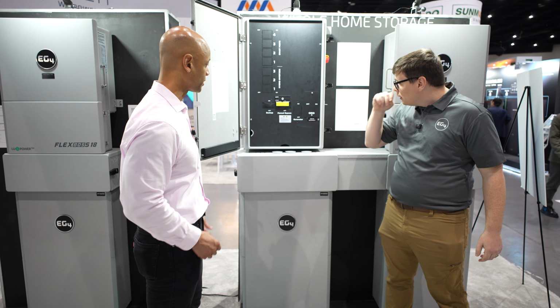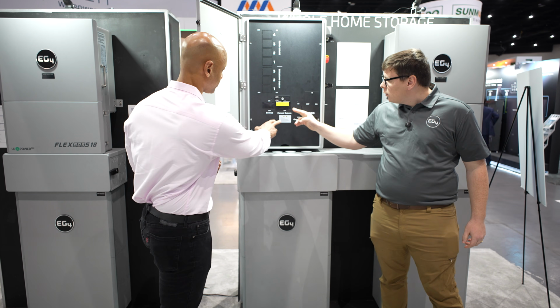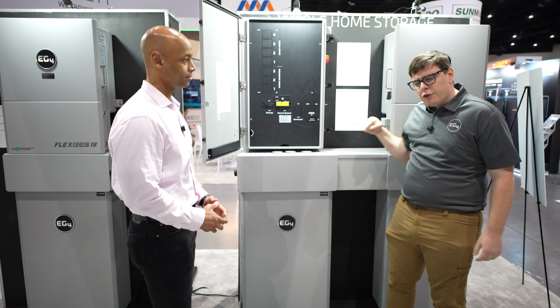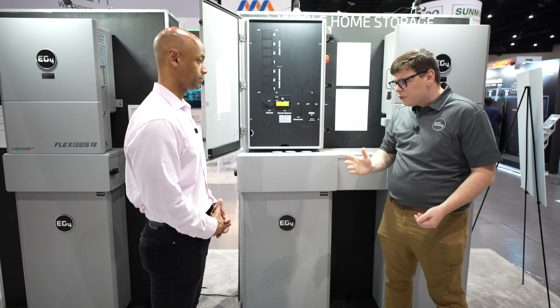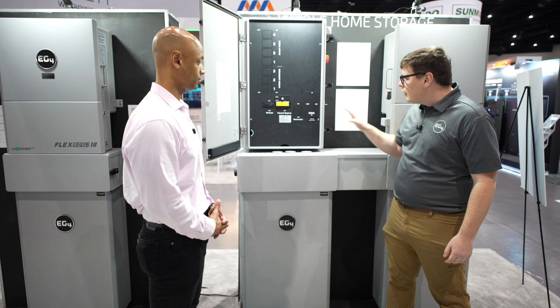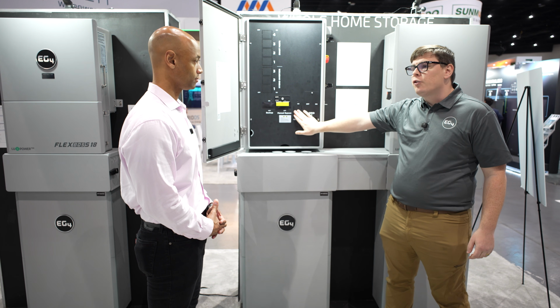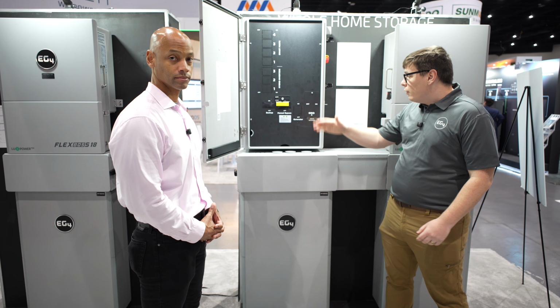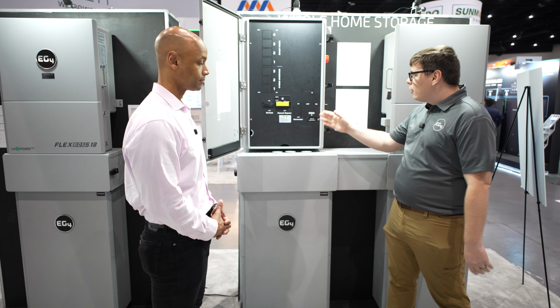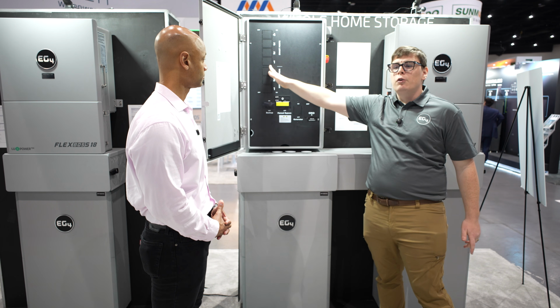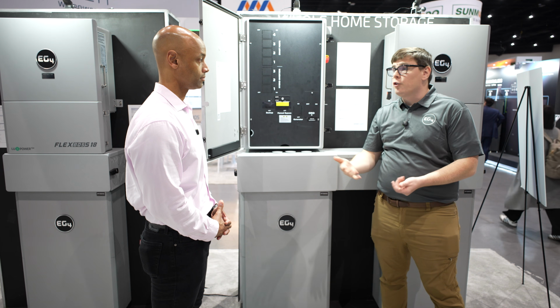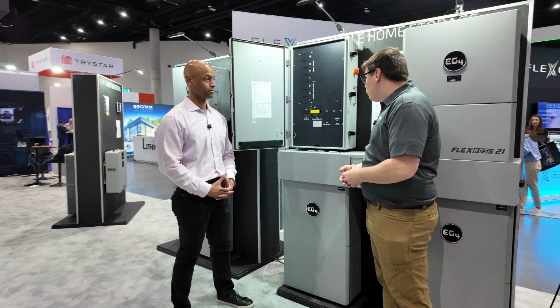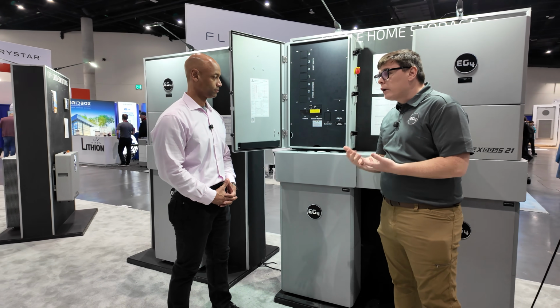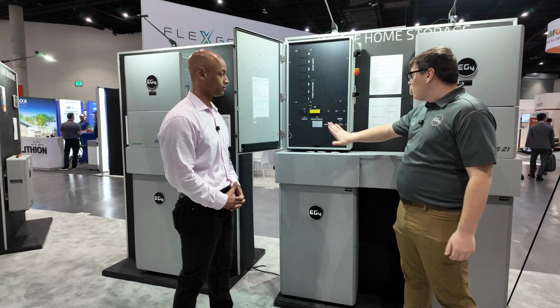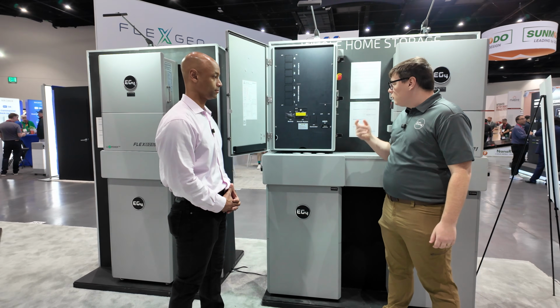What are some of the other functions that the GridBoss supports here? I see a bypass. The manual bypass, that changes your 200 amp transfer switch, is built into this solution. And it also has the generator integration built on here, so you can add in a separate generator directly into here. You can load shed here, and you can also AC couple. So you can do all 3 at once. Whatever the customer needs, whatever you're looking for as a homeowner, this is a solution for everything.